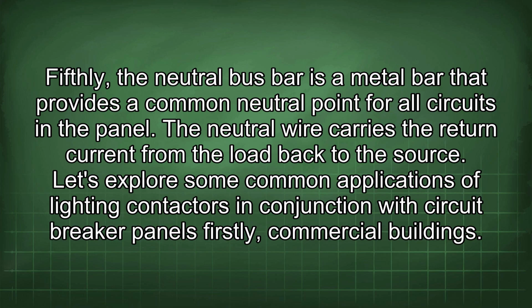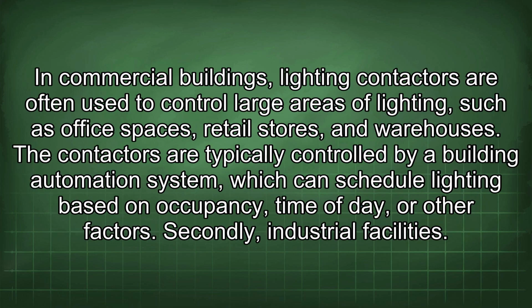Let's explore some common applications of lighting contactors in conjunction with circuit breaker panels. Firstly, commercial buildings. In commercial buildings, lighting contactors are often used to control large areas of lighting such as office spaces, retail stores, and warehouses. The contactors are typically controlled by a building automation system which can schedule lighting based on occupancy, time of day, or other factors. Secondly, industrial facilities.